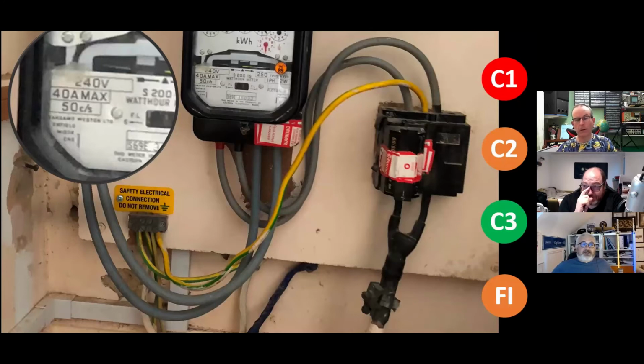I actually got, this is quite sad, I actually got the regional manager for the DNO around my house and argued with him over the state of the head and everything else around it. And he didn't disagree with anything I said, because he said, yeah, you need to get a new meter rated 100 amp. We'll put you in a new GRP one. And yeah, that's what they ended up doing.